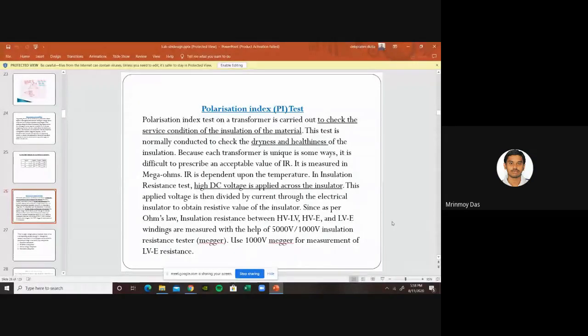So when we use the Megger on the HV side, we use the 5000 volt Megger, or 5 kV Megger, and we use it for 10 minutes. And for the LV side, we use the 1000 volt Megger, for 10 minutes. And then again on the HV side we use the Megger and do the test for 1 minute.